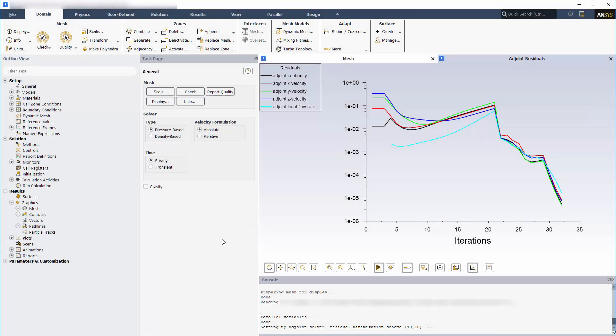In part 1 of this video series on redesigning the shape of an air duct, I used Fluent's Adjoint Solver to calculate sensitivity data for an observable that included both the pressure drop between the inlet and outlet, as well as the uniformity of the outlet velocity.